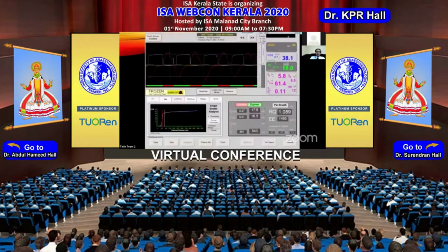This is a small device which measures volume capnography, giving you a volume capnogram with all its components. And this device is very interesting: it is a side stream capnograph. Most volume capnography devices are mainstream, whereas this is a side stream capnograph which has been tailored to give these values. As you can see, it gives you the CO2 waveform. It is also plotting the respiratory flows, which I alluded to when we were talking about where expiration actually ends in a capnogram. And it gives you all the values of physiological dead space.